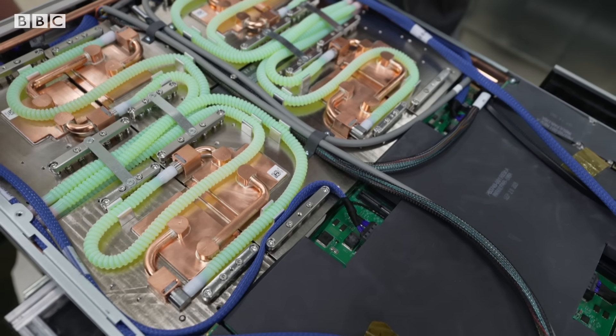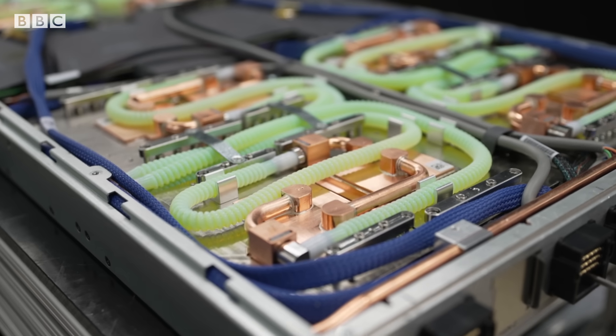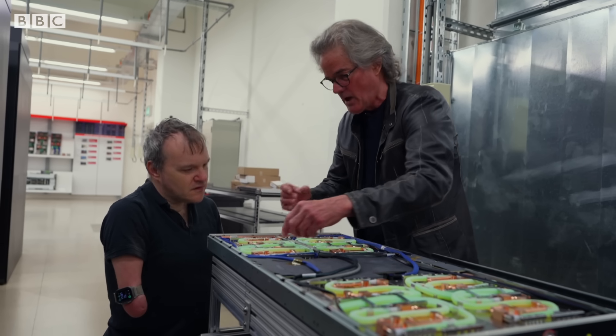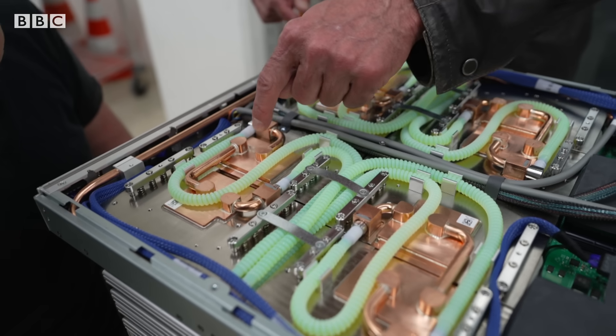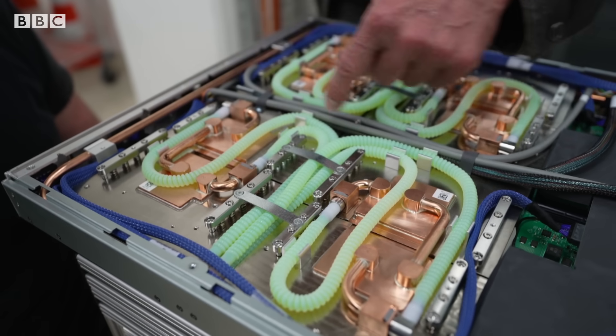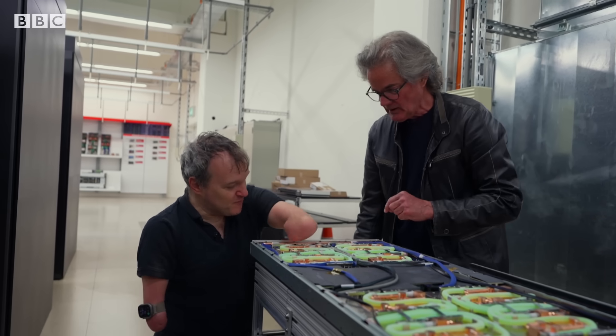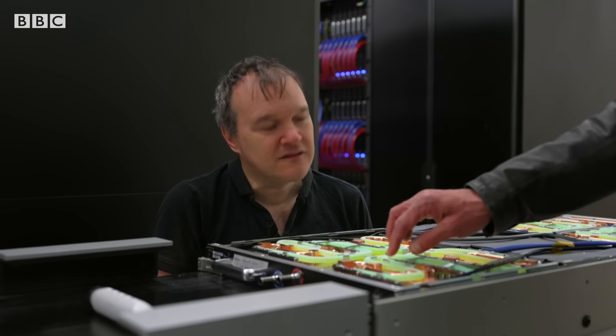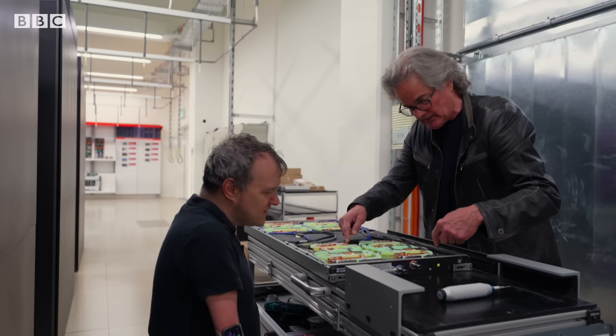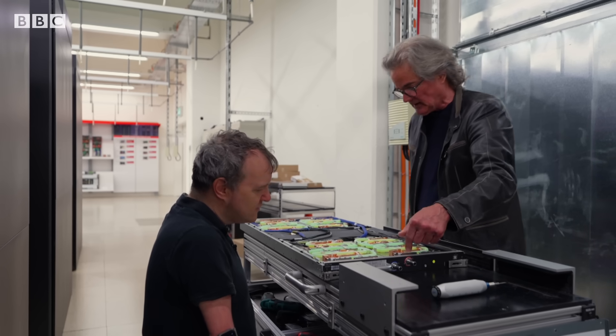This is the inside of one of the many blades in the system. Here you have a Grace and a Hopper processor — a multi-core CPU and an H100 GPU. They consume a lot of power, so liquid cooling goes directly on the processor. These are copper pipes: cold water comes in here, is distributed, and the warm water goes back out into the data center.